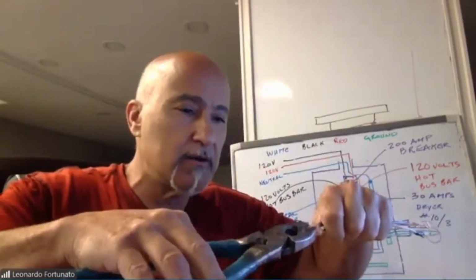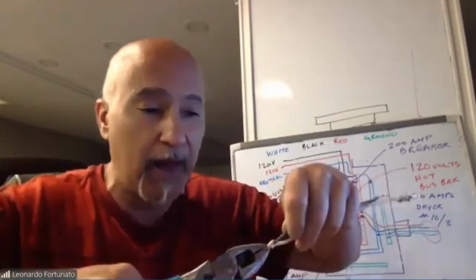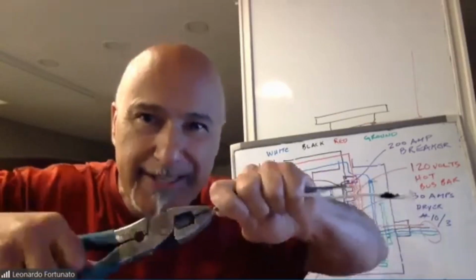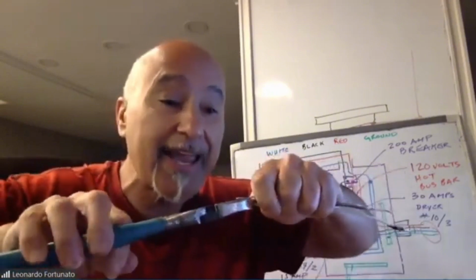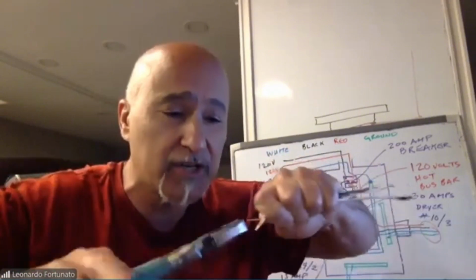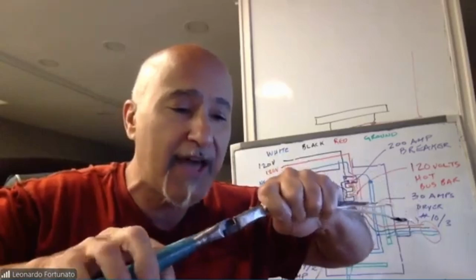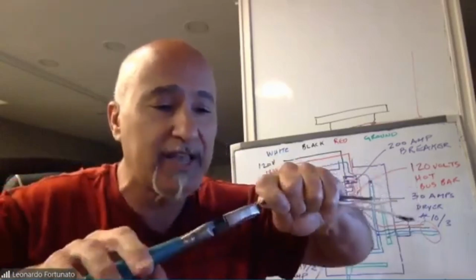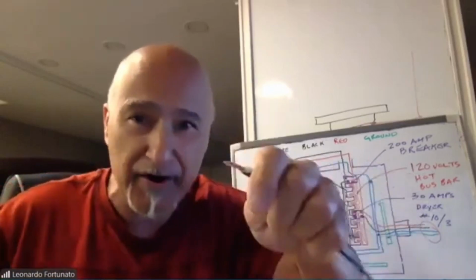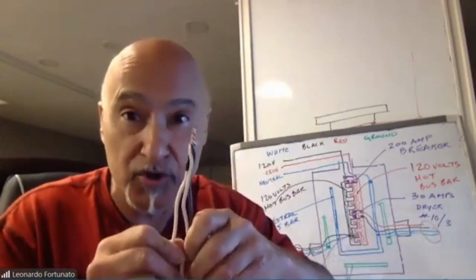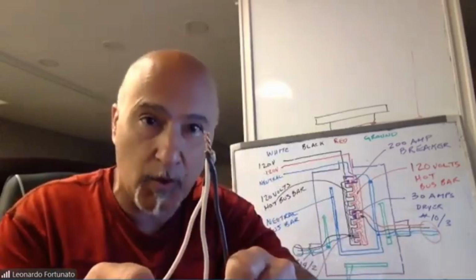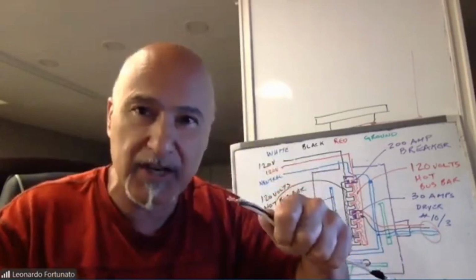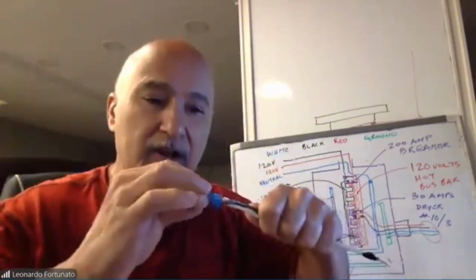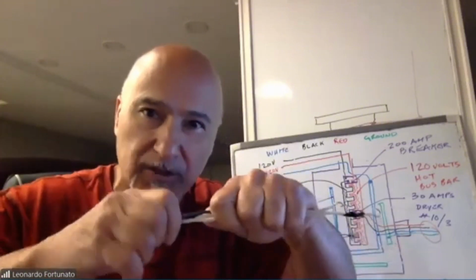When we make connections with wires, before you put your wire nut on, put your wires together in your linesman plier, and then twist them together in a clockwise orientation. Always twist your wires together in a clockwise orientation. Now that these wires are twisted together, they will not come apart, because when you put the wire nut on, you're also turning it in a clockwise orientation.